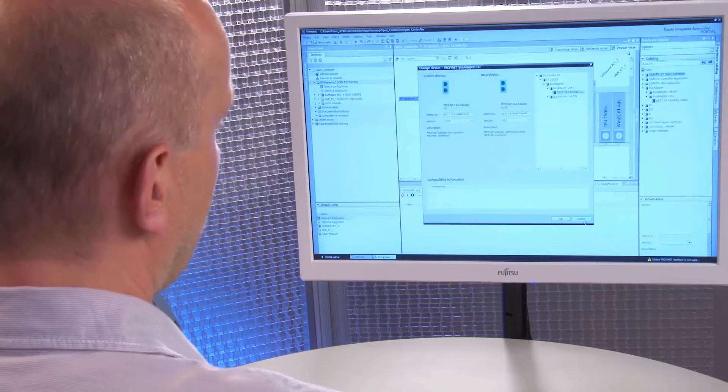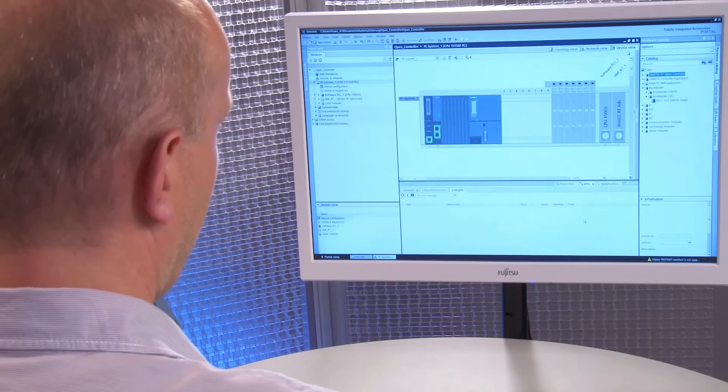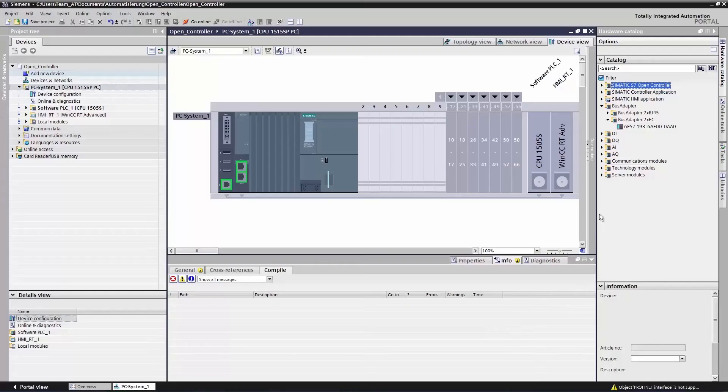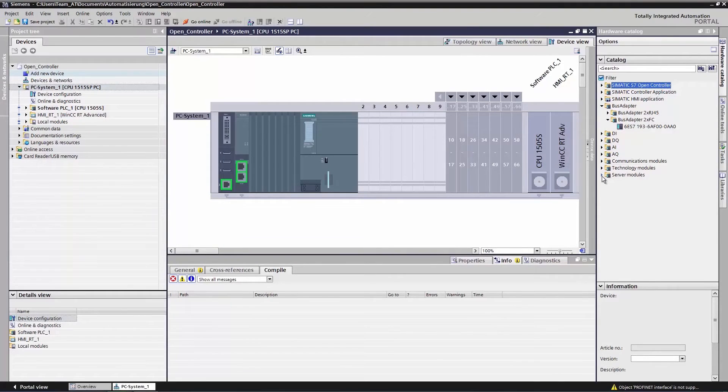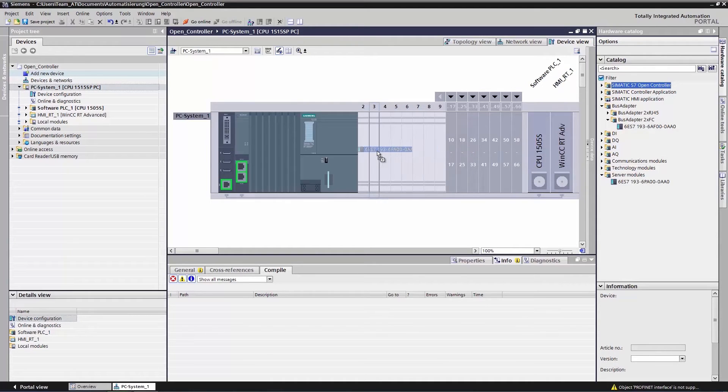We don't want to do this right now, so we click Cancel instead. As a final step in the hardware configuration, you can now configure the server module which completes the CPU with the peripheral modules. You will find the server module in the assembly catalog in the section Server Modules. You can move it to slot 2 using drag and drop. Should you ever forget this step, then the TIA Portal will automatically insert it for you during project generation.